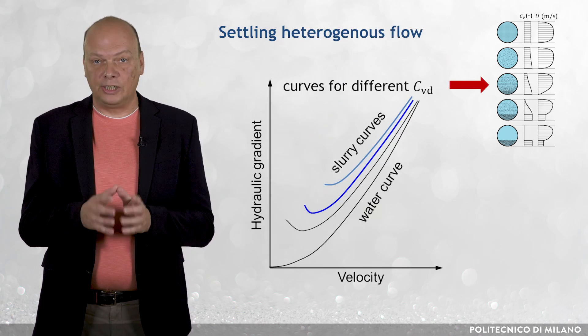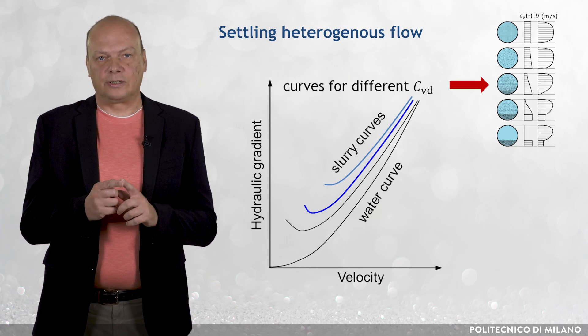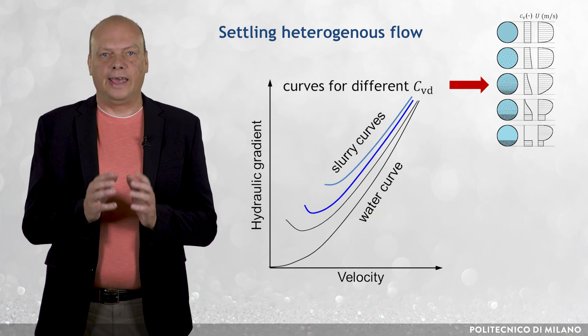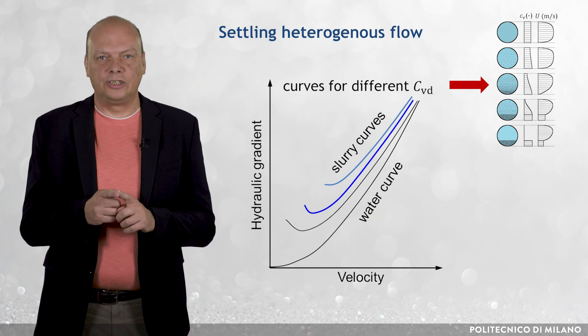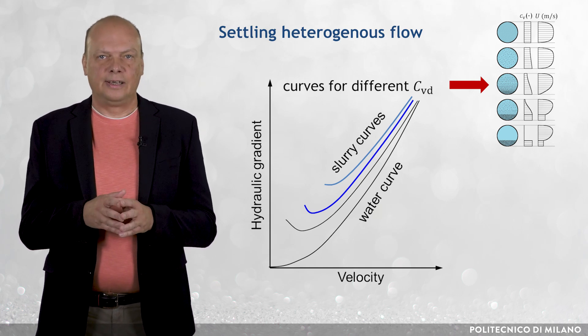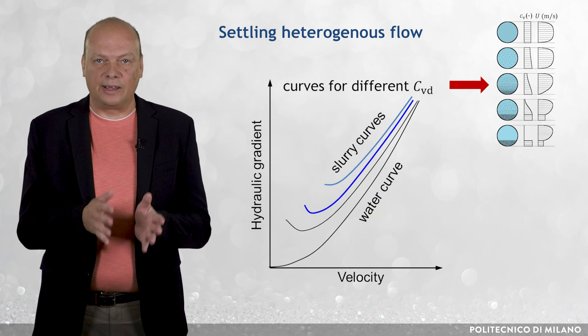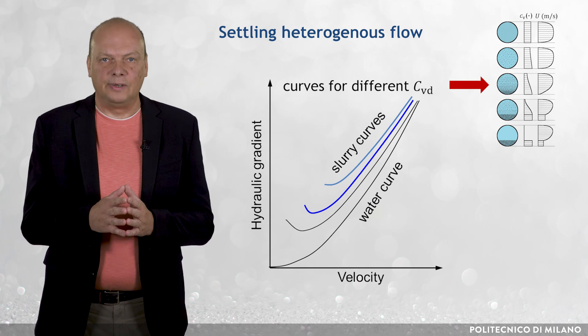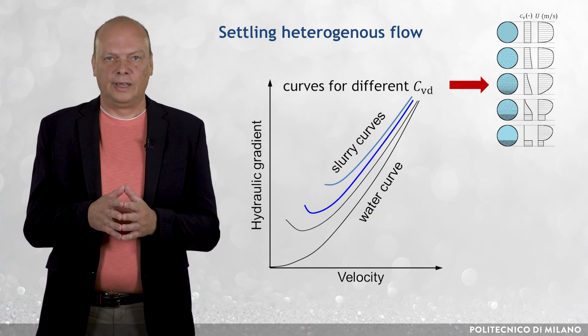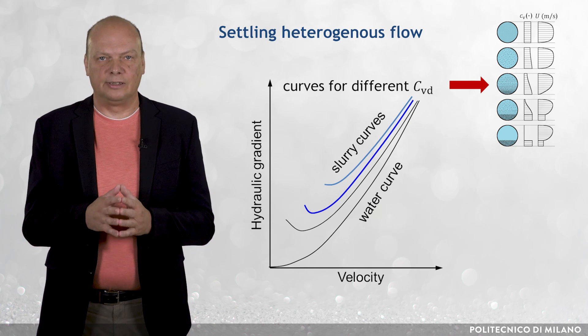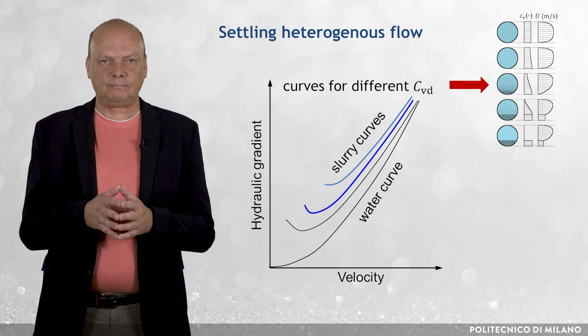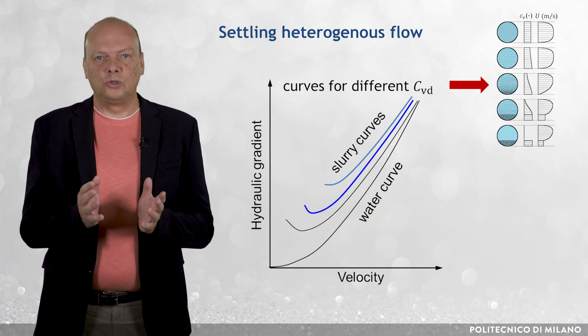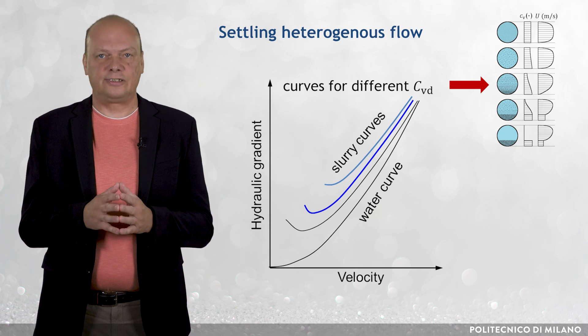In heterogeneous flow, a pipe characteristic curve for slurry flow of constant delivered concentration exhibits a minimum point. The change in the trend of the hydraulic gradient with decreasing velocity, passing the velocity at which the gradient is minimal, is associated with increasing stratification of the flow and the establishment of a granule bed at the bottom of the pipe. The velocity at the minimum is usually close to the deposition limit velocity, but those two velocities are not necessarily the same.